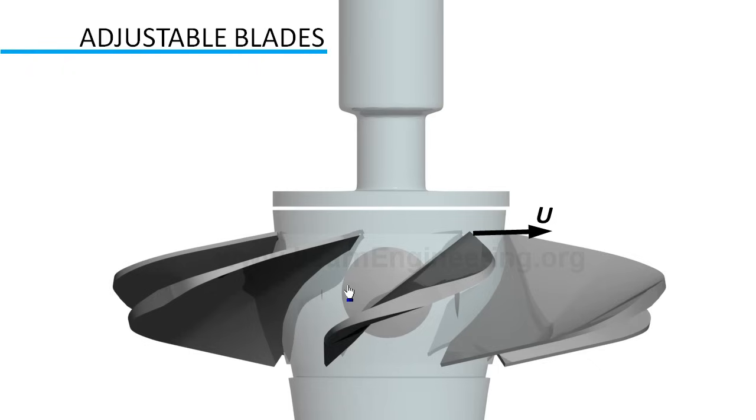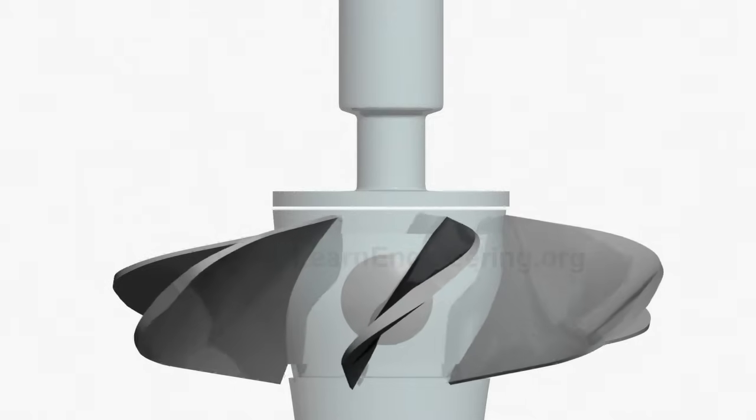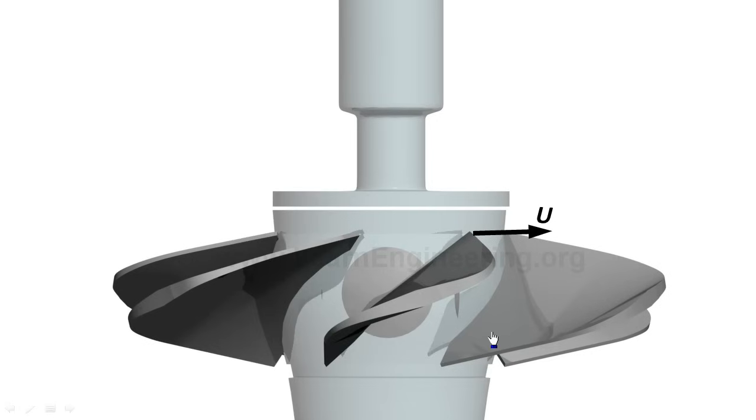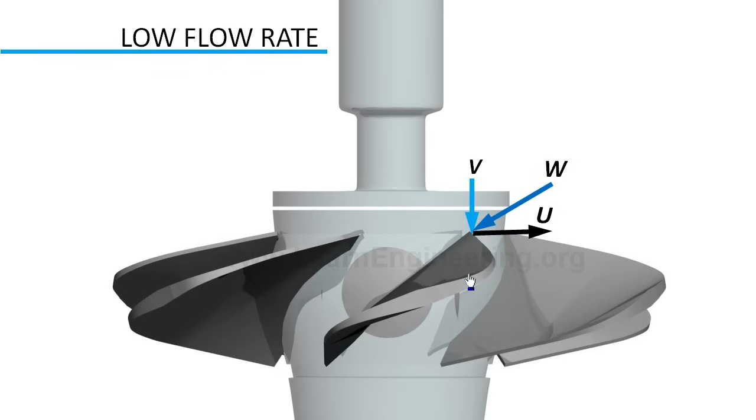When flow rate is high, relative velocity of flow will be more axial, so blades should pitch vertically. If flow rate is low, relative velocity of flow is more tangential, so blades are pitched in tangential direction.